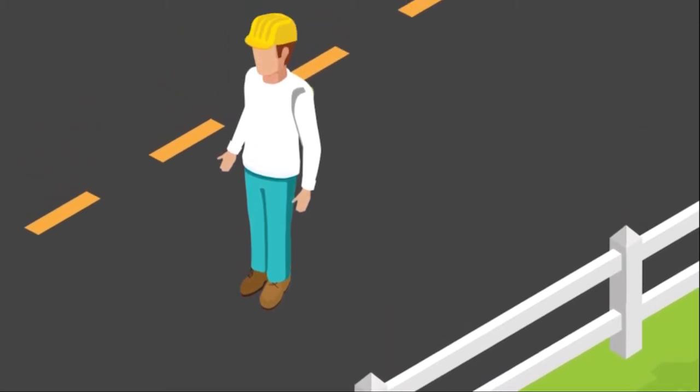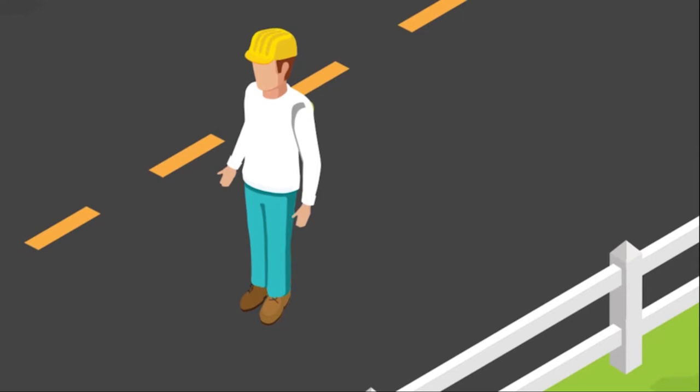The ground could be energized, so by keeping your feet together and shuffling away, you decrease the chance of electrical current entering your body through one foot and out the other.